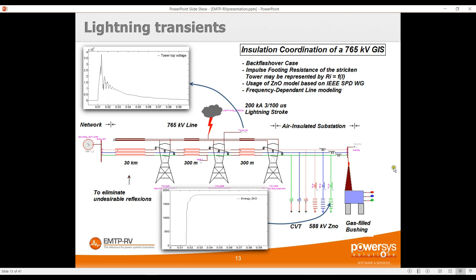Applying the lightning strike, we look at the voltage at different points of the substation and compare with the BIL of the equipment. We can see the voltage at the tower top — initially nothing, then the lightning strikes and we see oscillations due to waveform propagation through the towers and substation. We can also check the energy through the surge arrestor and verify it is properly modeled. Other studies include the rate of failure of the substation due to lightning and the influence of the grounding resistance of the towers.